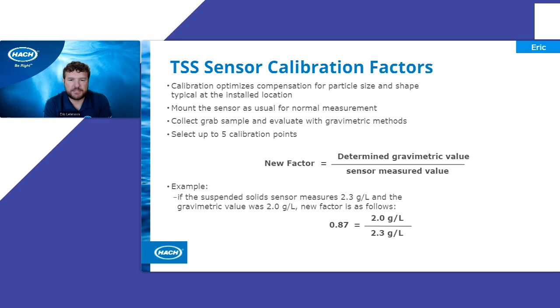So Carlos had mentioned previously the gravimetric lab procedure where you're weighing out the filter, you put it in an oven, you dry it out, and that's your gravimetric lab procedure. What we do for the calibration of the TSS probe is we pull a grab sample right next to the probe that's mounted in line. We'll capture that value on the sensor itself, take that sample to the lab and determine what the gravimetric TSS result is. And then that allows us to enter a factor into the probe. So now we're taking your sample, your matrix, determining the TSS value, and then entering that factor into the probe. So that's how we get the TSS rating versus just a single point NTU calibration.